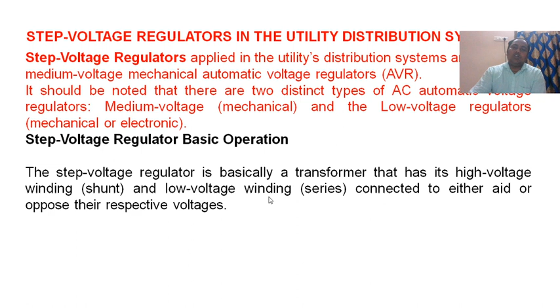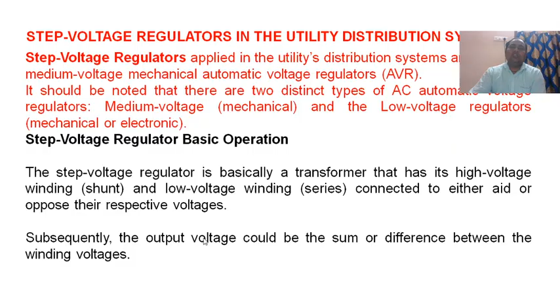Step voltage regulator basic operation. The step voltage regulator is basically a transformer that has its high voltage winding and low voltage winding connected to either aid or oppose the respective voltages. Subsequently, the output voltage could be the sum or difference of the winding voltages. For example, if the transformer has a turns ratio of 10:1 with 1000 volts applied to the primary, then the secondary voltage will be 100 volts. Adding or subtracting using the connection mentioned above, the output voltage would be 1100 volts or 900 volts respectively. So the variation is 100 volts, step up to 1100 or step down to 900.